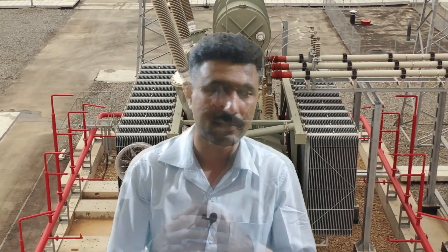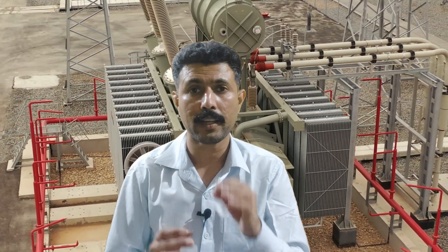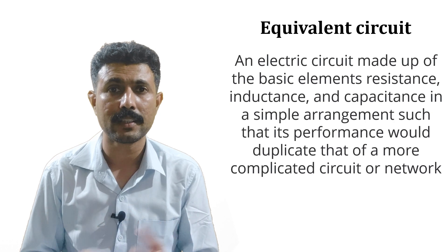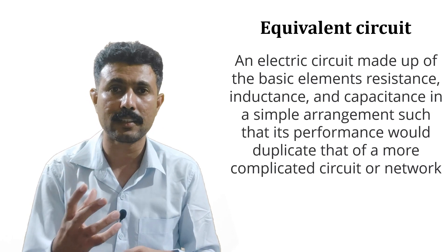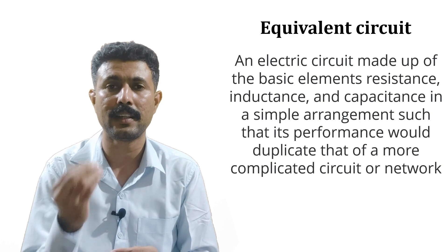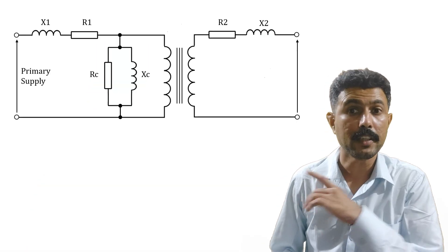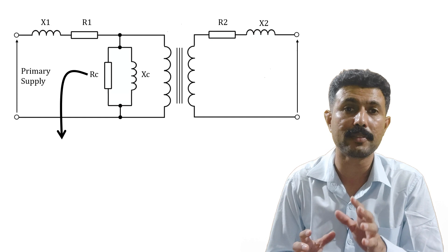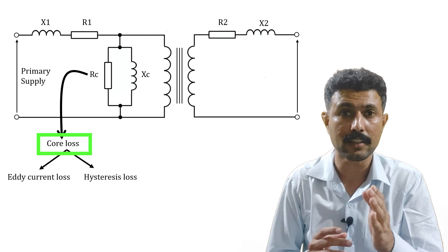Now we are heading towards the second question: why does the winding burn out? To understand this, let's look at the equivalent circuit of a transformer. The equivalent circuit is a simplified circuit representing the resistance of the winding, inductance of the winding, core loss, and copper loss, all in resistance and inductor form. The RC resistance in the equivalent circuit represents the core loss of the transformer, which consists of eddy current loss and hysteresis loss. This core loss depends on frequency, and the frequency of DC is 0 Hz, so the core loss becomes zero — we can remove that component.